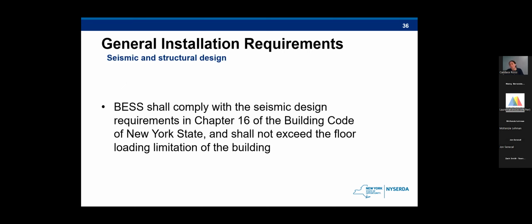So moving along, we have the seismic and structural design requirements. This is pretty standard. The installation will have to comply with the seismic design requirements in Chapter 16 of the International Building Code and shall not exceed the floor loading limitation. Once again, I think the need for this is pretty obvious.